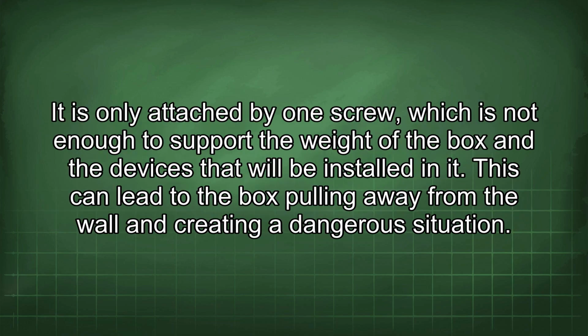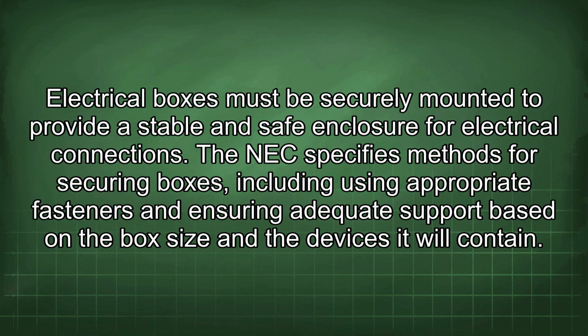It is only attached by one screw, which is not enough to support the weight of the box and the devices that will be installed in it. This can lead to the box pulling away from the wall and creating a dangerous situation. Electrical boxes must be securely mounted to provide a stable and safe enclosure for electrical connections. The NEC specifies methods for securing boxes, including using appropriate fasteners and ensuring adequate support based on the box size and the devices it will contain.